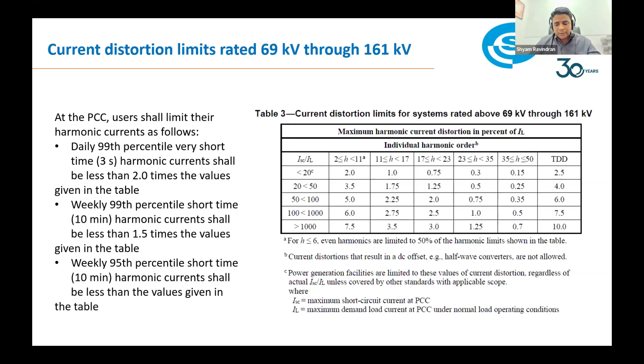For the customers having a system rated voltage of more than 69 kV up to 161 kV, you will see that the TDD value is slightly reduced here, but that's how the system actually works. Whenever we did PQ audits for the large bulk consumers, the huge manufacturing facilities, they were not actually having harmonics at the PCC level, because the impedance of their system was much higher because of their higher rated incoming transformers. So things were quite sophisticated even for them way back then.